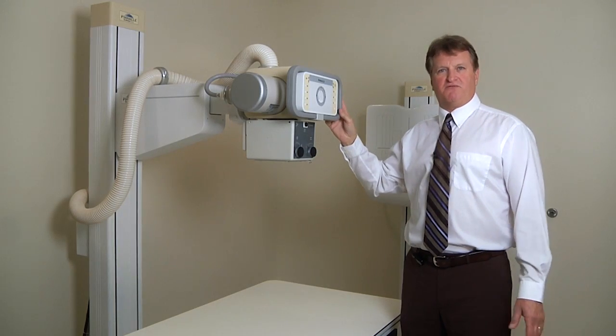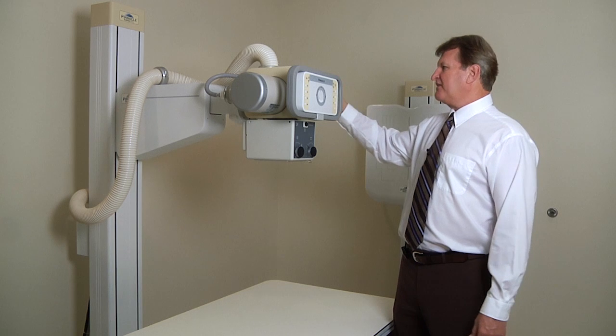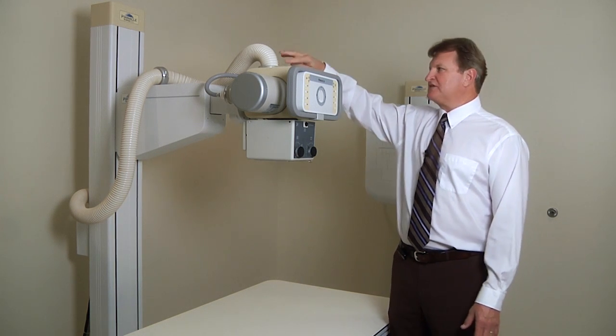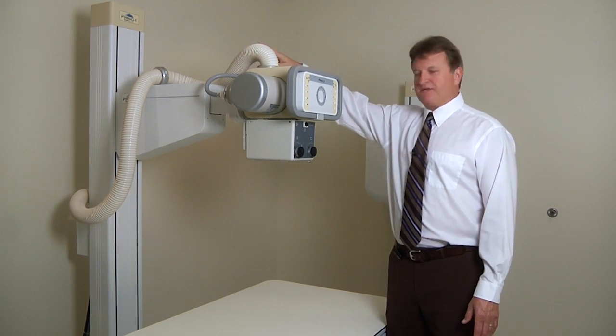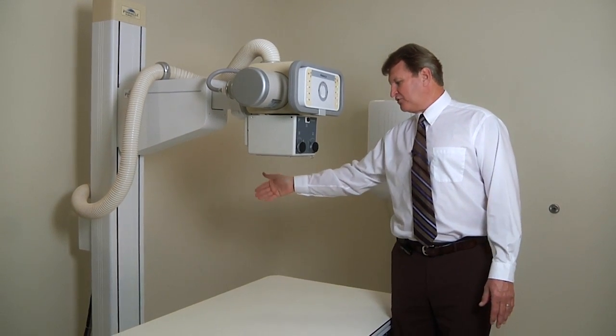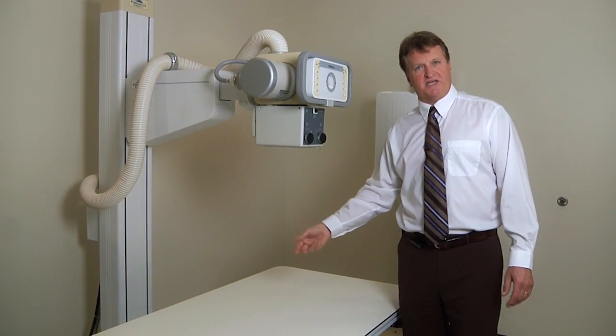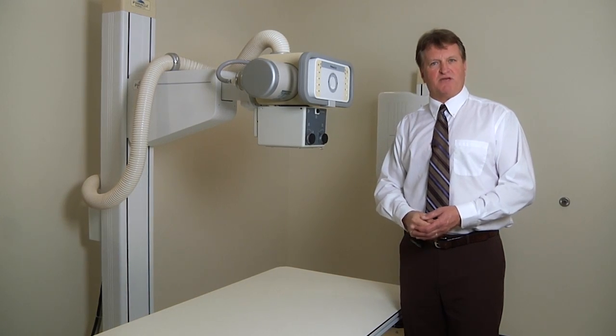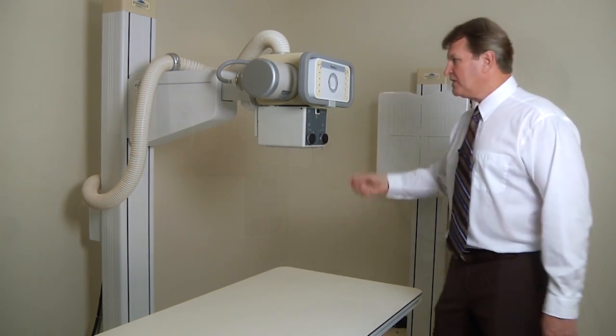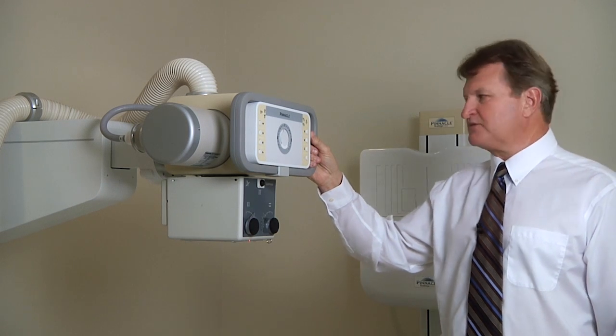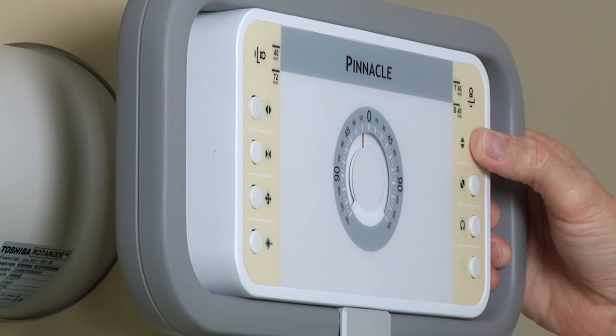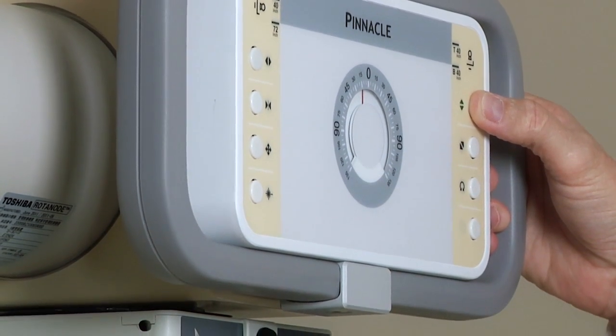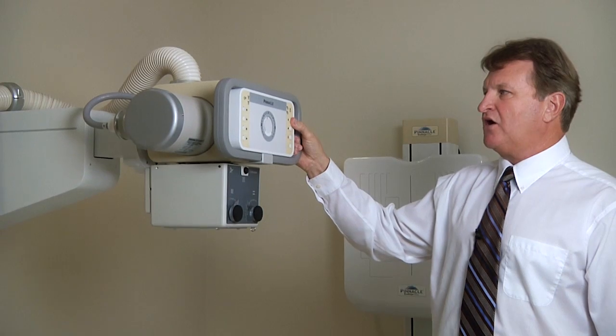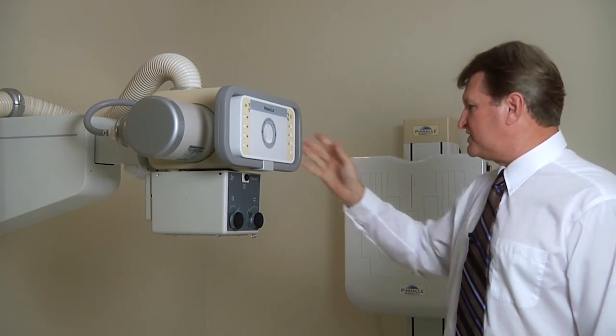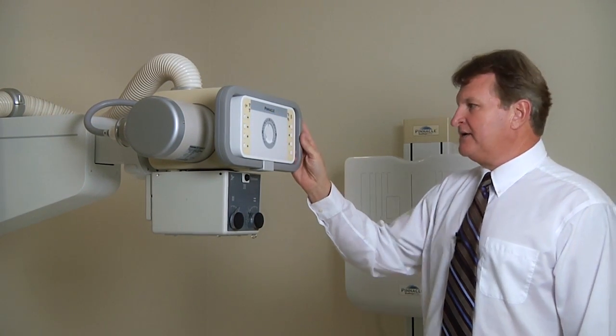Our fully functional floor-mounted tube stand has all of the high voltage cables, rotor cables, etc. concealed within the corrugated hose. All the interconnecting cables go through a channel at the bottom of the floor stand and are directly plugged into the back of the table for a secure installation. Vertical, longitudinal, and transverse movements are all controlled by push buttons on the front of the hand grip. 40 inches to the bucky and to the tabletop are indicated by LEDs. Also, the 40 and 72 inch to the chest board are indicated by LEDs.